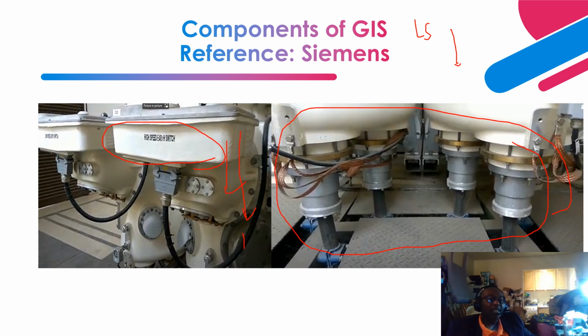That is where the high-speed earth switches come into play, because the switchgear, the GIS, is basically the interface with the external side. This is just an example. You have the external load side, and the external incomer side. Those are where the high-speed earth switches are located, basically to take all the energy from phenomena like lightning surges, capacitively coupled voltages, and overvoltages to ground, to prevent them from cascading into other components.